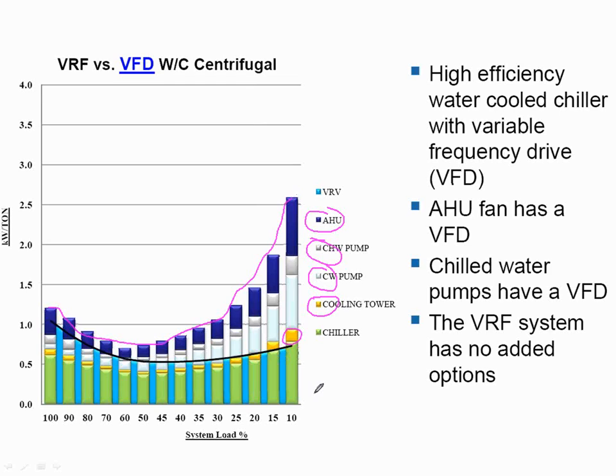And this particular example was using a centrifugal chiller with a VFD on the compressor, VFD on the air handler fans, VFD on the water pumps, right? So you can see what's happening here is that in many cases, this blue bar, the fan energy, is definitely the big gorilla in the room. And having a VRF system that doesn't have a lot of fan energy to begin with, and that energy is included in its rating points, is pretty beneficial.